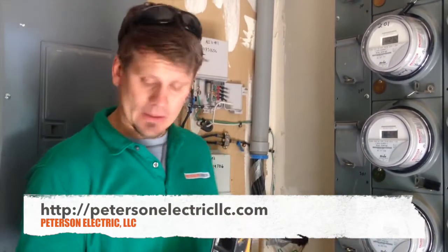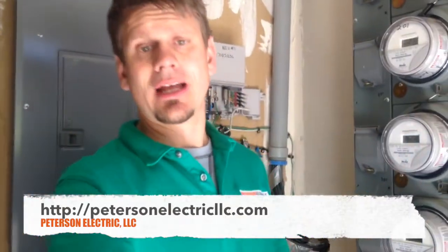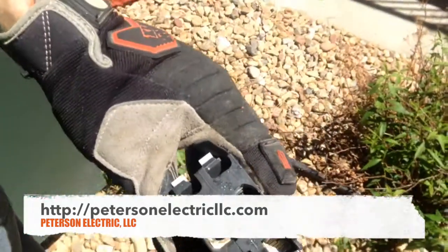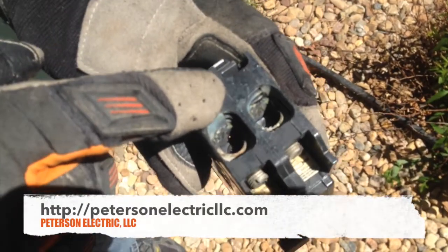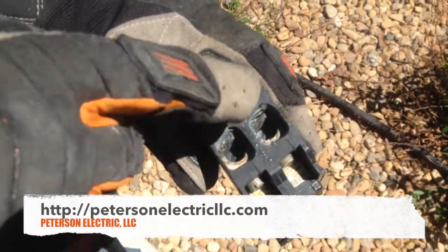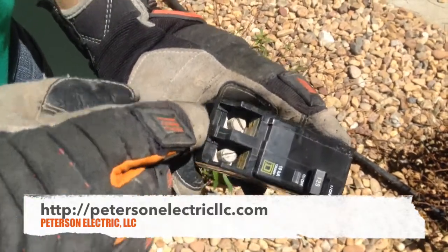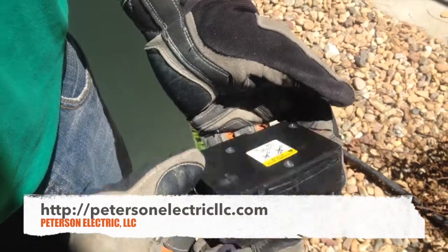So out here on the breaker, I was reading at about 104 degrees, and it was climbing. I didn't hear any crackling and none of the insulation was melted. But here's what I finally found, and it was really hard to see until you pulled the breaker. Once we pulled it, we could see that there was charring more on this side, B phase, than A phase. And then the thread started getting really tight to get out. So this breaker was just about to go down the road, and we caught it just in time.